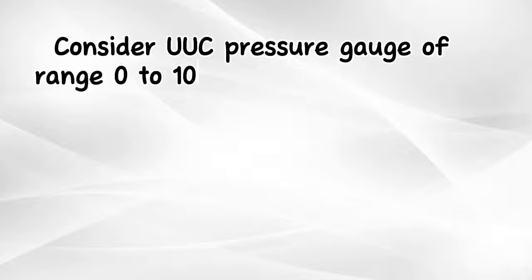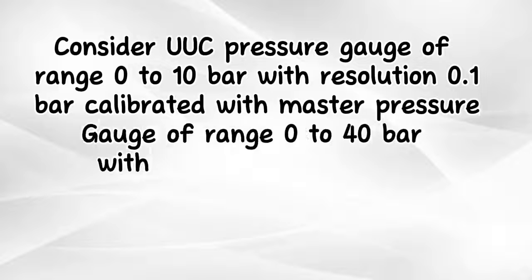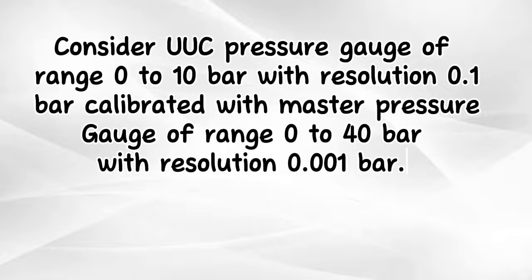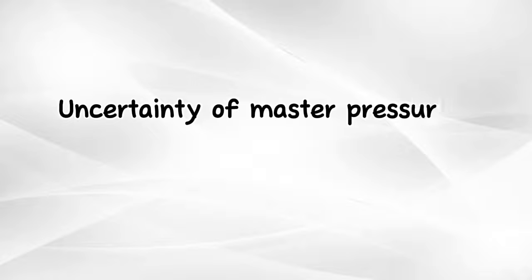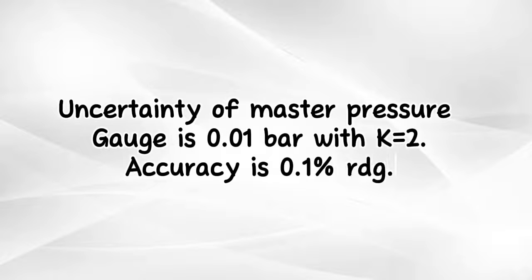Consider UUC pressure gauge of range 0 to 10 bar with resolution 0.1 bar calibrated with master pressure gauge of range 0 to 40 bar with resolution 0.001 bar. Uncertainty of master pressure gauge is 0.01 bar with K equals 2. Accuracy is 0.1% RDG.